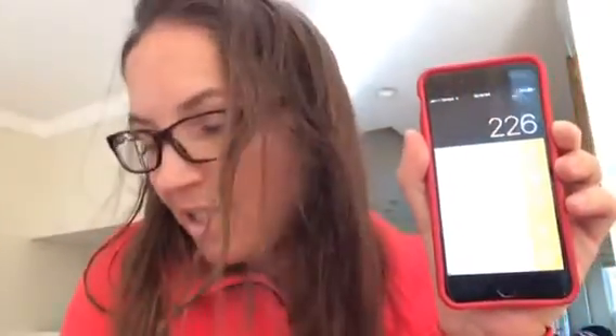So now I can add or subtract 58.8 from that 168 to give myself a range. So I'm going to call it 58. I'm going to say 168 plus 58 is a 226. I'm not going to do the subtraction because my number's not lower. Okay, so I'm just going to go to the upper end of the range, and the upper end of the range is a 226. And I said, let's pretend that the BG that I've just gotten with my finger stick is a 202. Well, that's under that upper range, which means that this is a successful calibration number, and it'll be fine. So I would go ahead and calibrate.